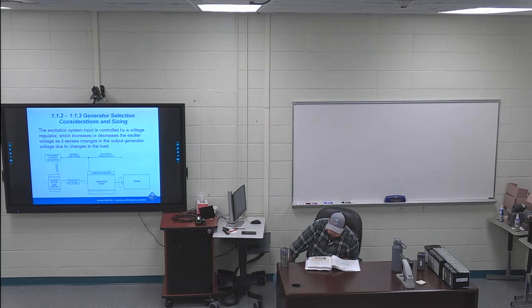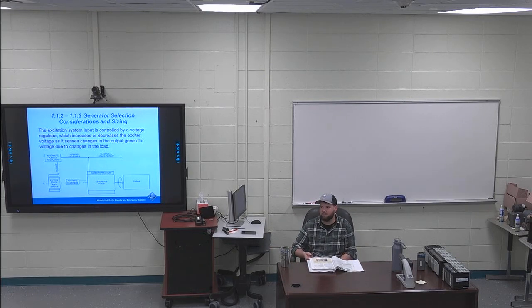Page 5, the bottom left, I've got the last sentence down there highlighted. Once the starting and running loads have been determined, it is common to add a margin factor of up to 25% for future expansion or to select a generator set of the next largest standard rating. So that's just saying don't size your generator to exactly what you have. Buy the next bigger size. Even for your houses, you can get a 2,000 watt generator, then it bumps up to 4, then 5, then 6,500, 8,000, 10,000 watt generators. They come in specific sets, so they're just saying buy the next size.